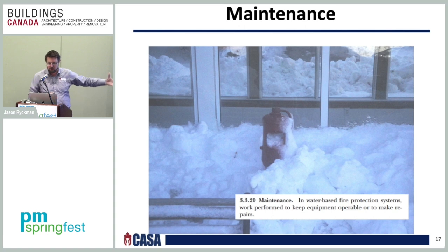Maintenance. Another fine example of maintaining the outside of your building. When you have fire protection devices such as this post indicator valve, maintenance is work performed to keep the equipment operable or to make repairs. Maintenance includes not only the required functions in the standard, but also practices and procedures recommended by the manufacturer, whoever that is. Maintenance is not always directly related to physical components of the system. It also includes day-to-day operations necessary to ensure that the system is accessible. So one of the biggest things is your fire hydrants.